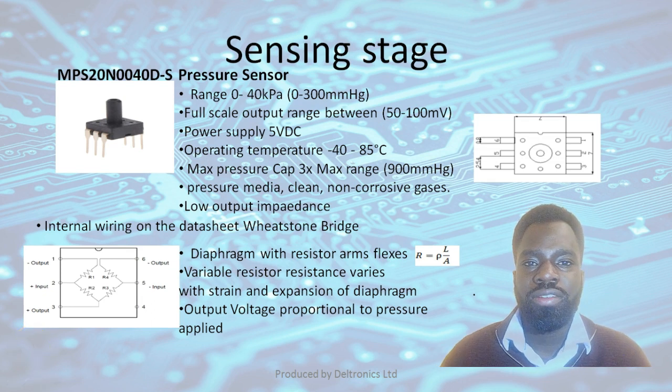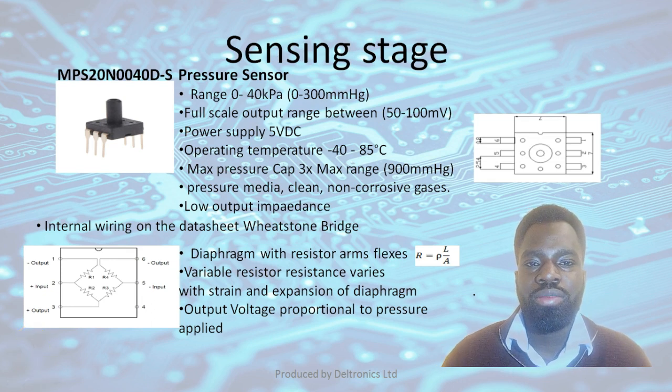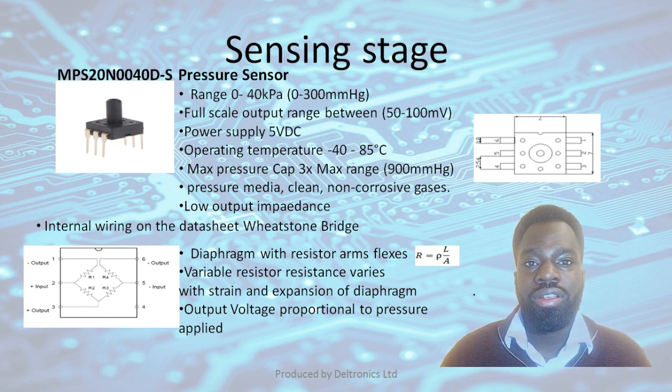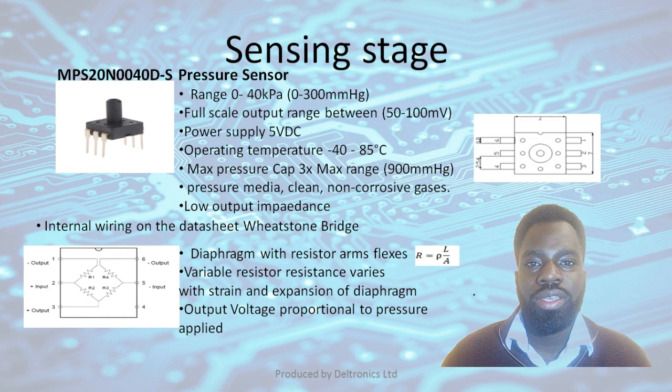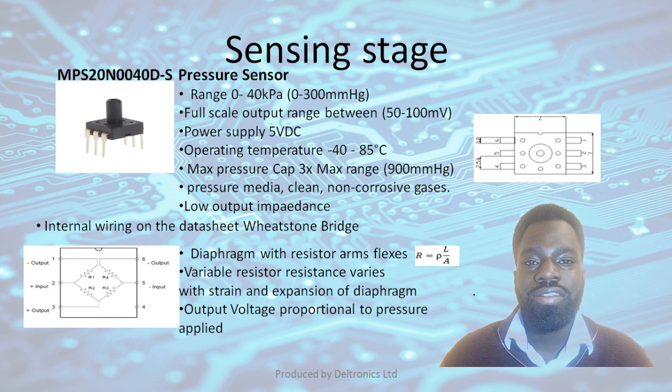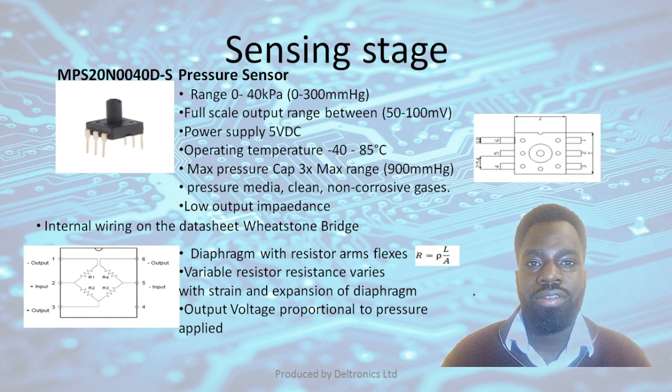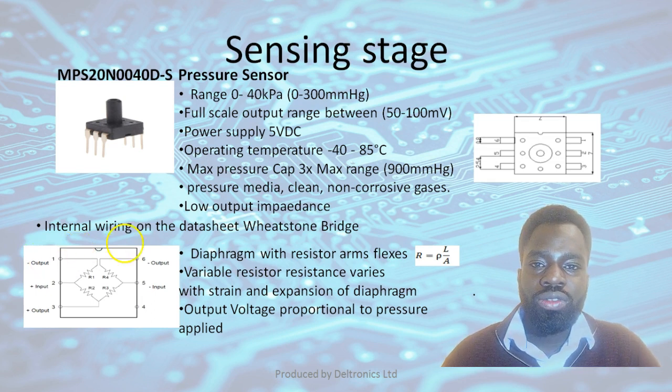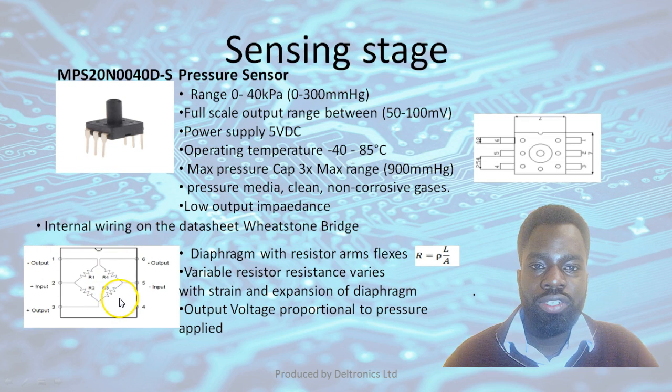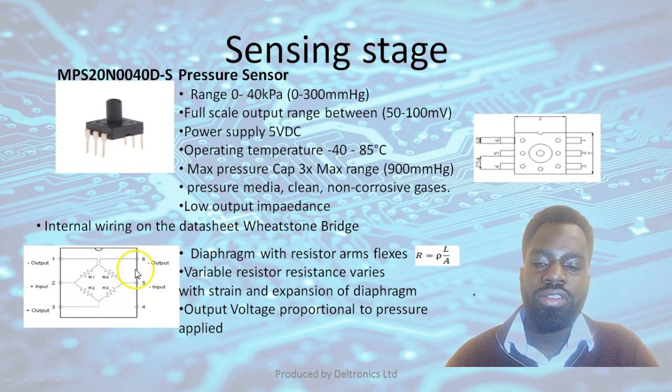The datasheet also specifies that the pressure sensor operates correctly between minus 40 to 85 degrees Celsius of ambient temperature. The datasheet also shows us the internal wiring of the pressure transducer. As you can see, the internal circuitry is in a Wheatstone bridge configuration.